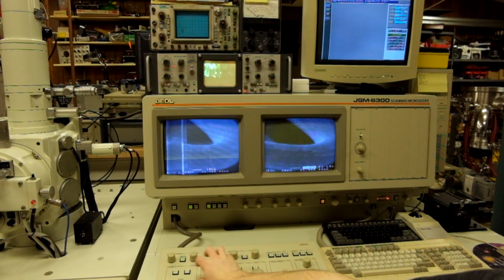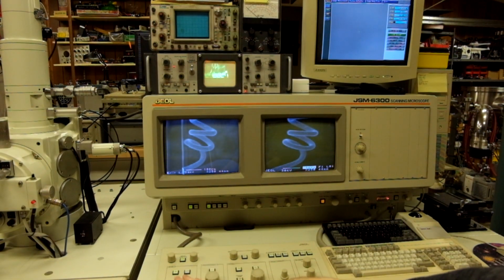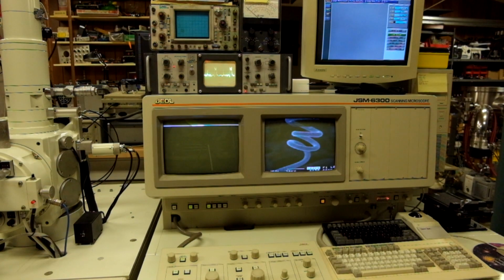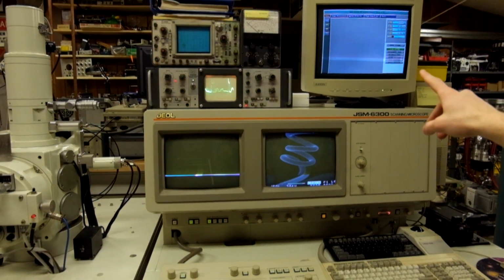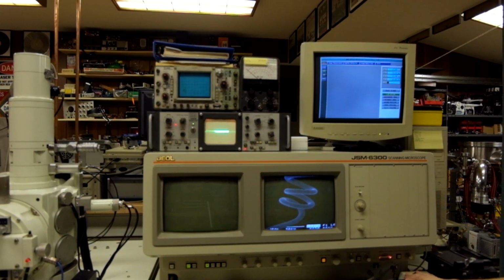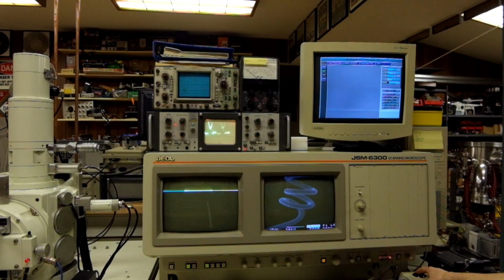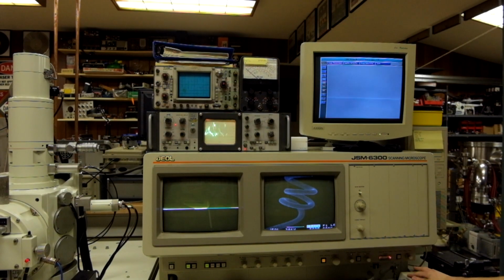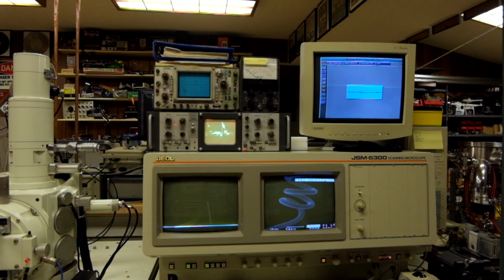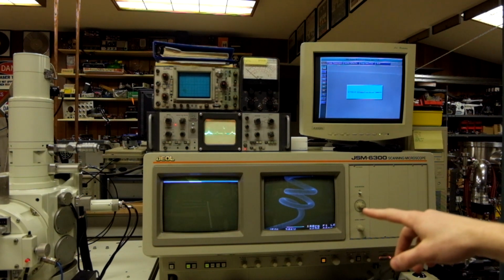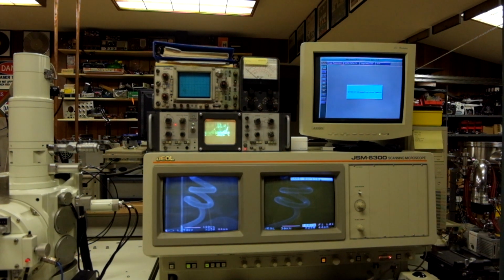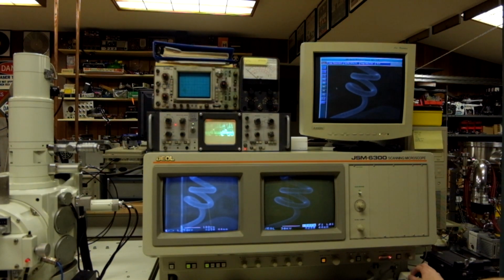I'm going to go back to a fast scan. I'm going to zoom out a little bit, and I'm going to slow scan that again. And then when I'm happy with the image, I can send it up to the digital computer, and then I could export it to a more modern computer. So I go to the imaging tab and hit receive, and it'll freeze the digital monitor there, and it'll send it over via SCSI cable to the ancient computer. And there we go, we have the image.